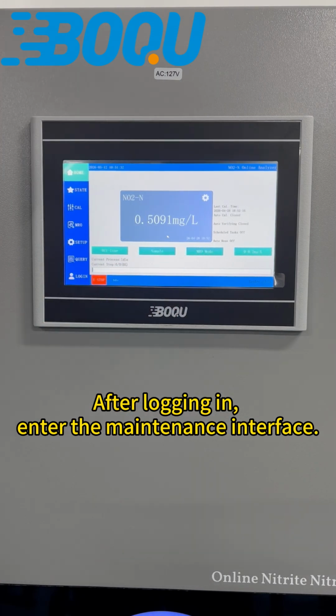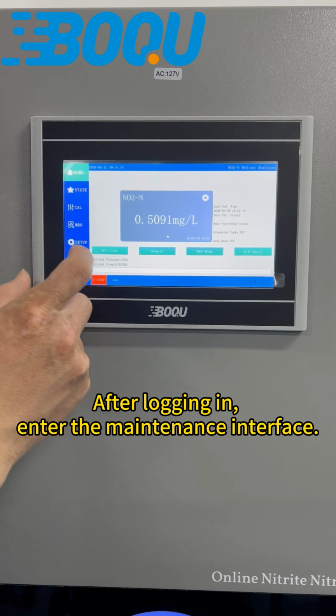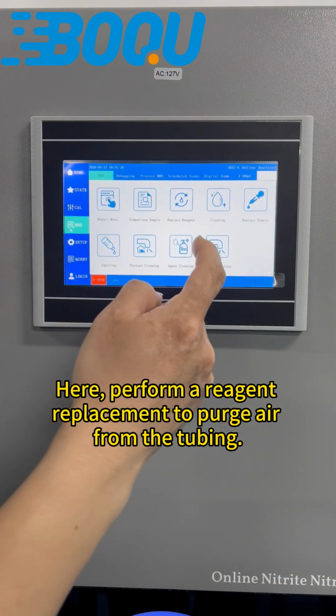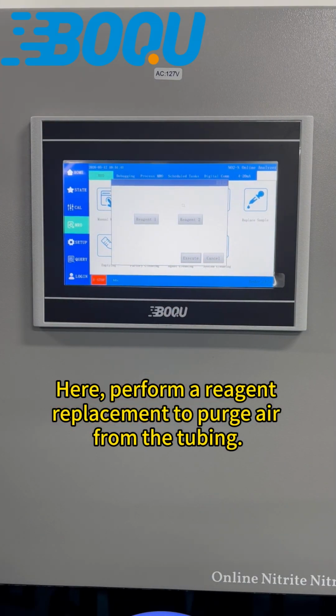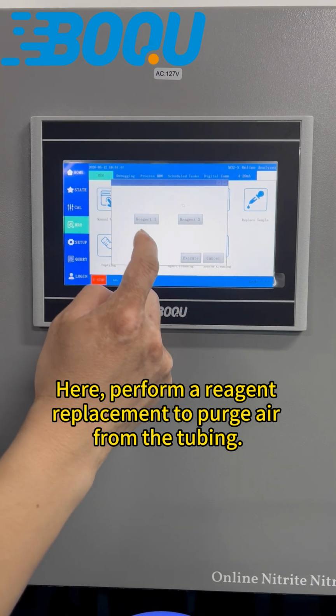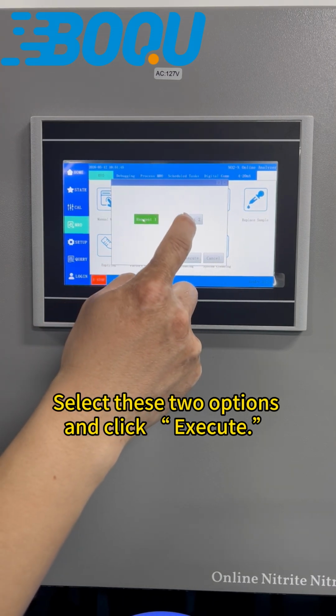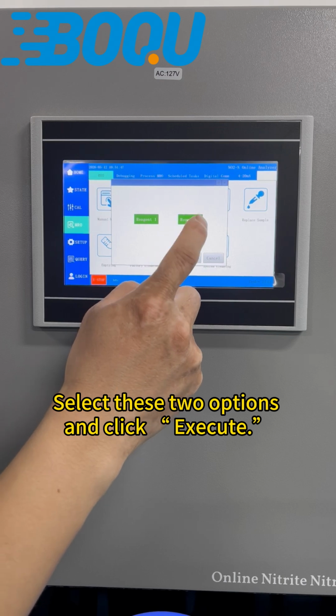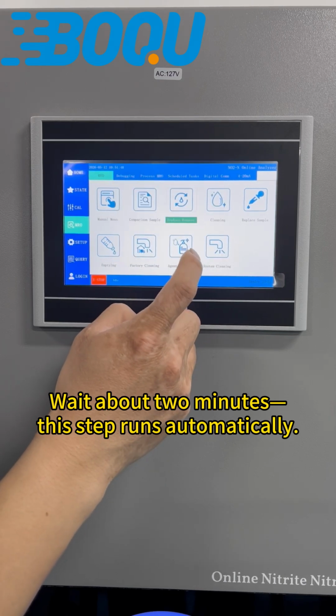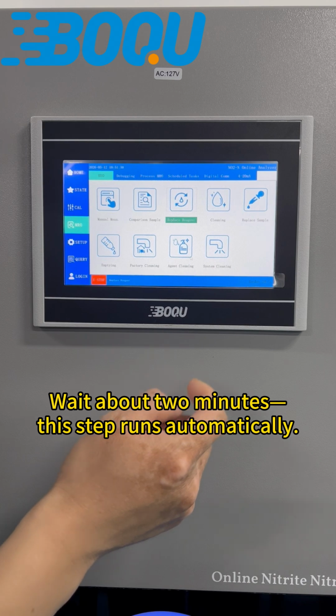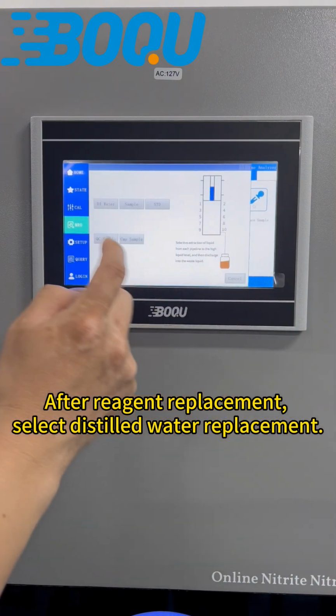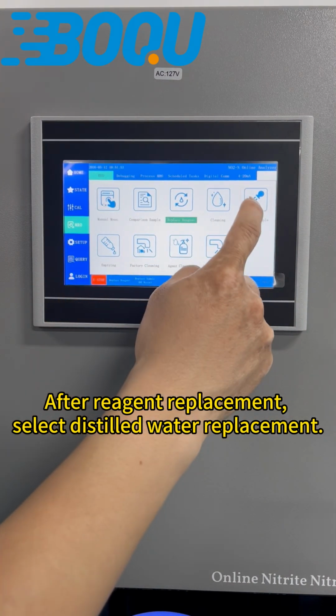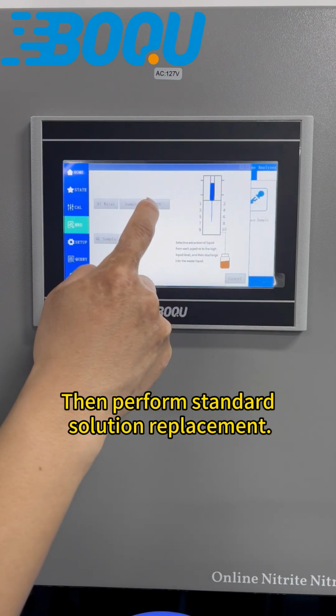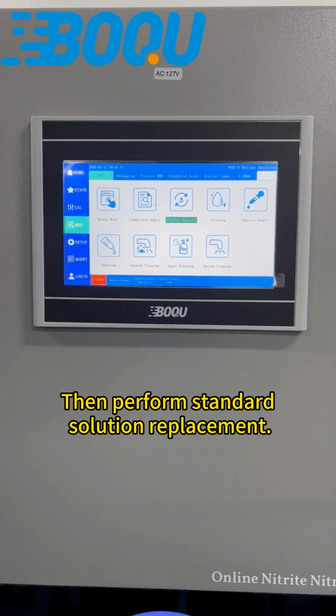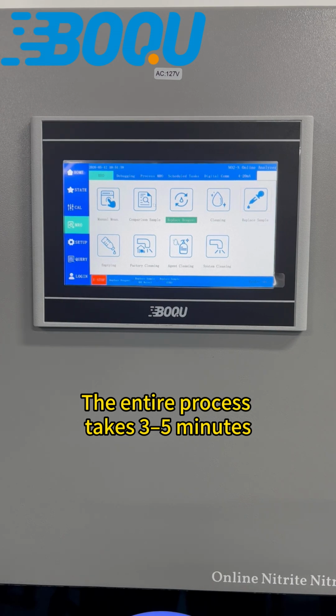After logging in, enter the maintenance interface. Here, perform a reagent replacement to purge air from the tubing. Select these 2 options and click Execute. Wait about 2 minutes. This step runs automatically. After reagent replacement, select distilled water replacement, then perform standard solution replacement. The entire process takes 3 to 5 minutes.